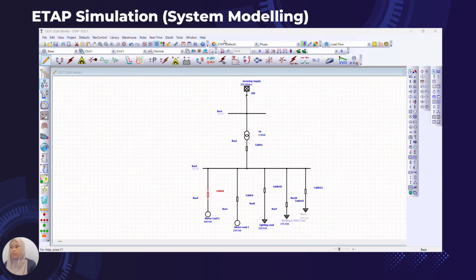TUKIMAN, my matric number AE220032. Today I would like to show you about the ETAP simulation. So, as you can see, this is our single line diagram. It consists of the power grid, the high voltage circuit breaker, bus bar, transformer, cable that connects the transformer to the switchboard, and also the main switchboard to the load. And lastly, we have the motor load and other loads like lighting load, welding load, and also the spare feeder for the future load.